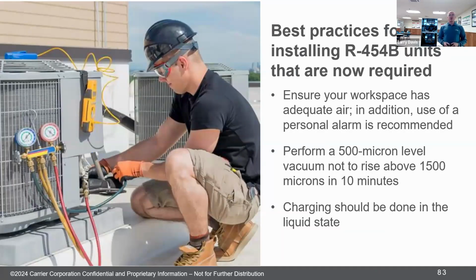Best practices when you're installing. If you're installing a new system, you want to make sure that wherever you're working, you have adequate air. One of the things they're recommending is having a leak detector turned on and sitting next to you while you're working. If that leak detector, which is rated for use with 454B, goes off, that is your notification that there's refrigerant present in the air, and you need to mitigate or dissipate that refrigerant as soon as you can.